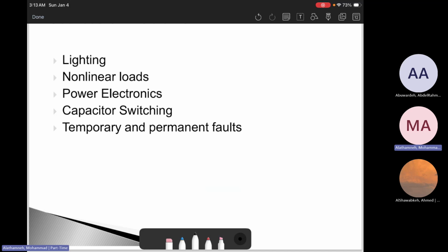So in practice, when we install a power quality monitor, we don't just record the data. If there is a problem, you will record a signature, but we need to record how deep the sag was, how long it lasted, which phase, and whether it was transient or oscillatory. Does it repeat every day? For example, is it related to the load every day at 2 p.m. or 1 p.m.? Or is it happening only during storms, which is weather related? Or is it happening because of customer behavior? This will help you diagnose the problem.